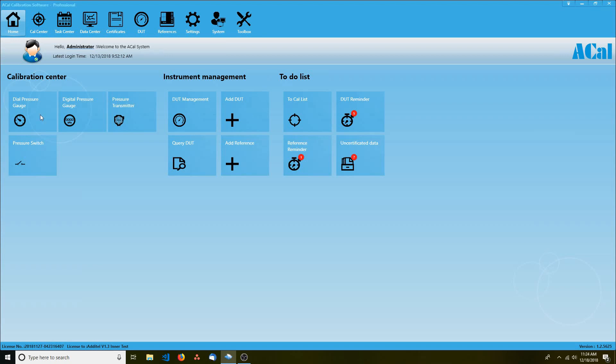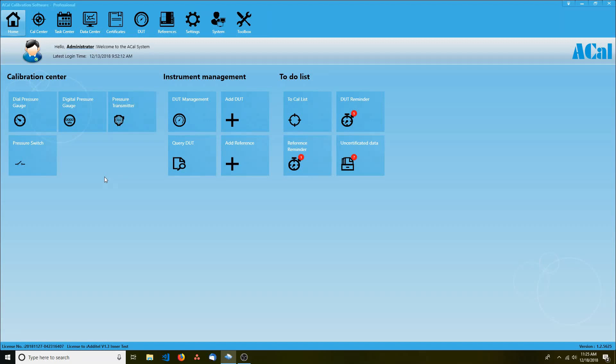If you travel back to the home screen, we'll take a look at the buttons too. The buttons on the left allow you to do a calibration for a specific type of instrument. You can also do this from the cal center, but I find the buttons to be more convenient.